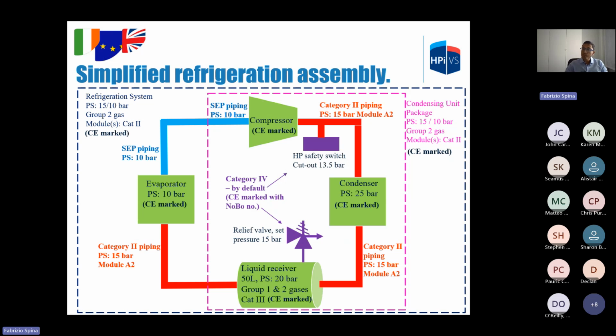This is a simplified refrigeration assembly. We can start with the compressor, already CE marked, so it is a bought item. We have the condenser, already CE marked, so it is another bought item. The liquid receiver, CE marked, so bought item. Category 3, PS 20 bar, suitable for group 1 or group 2 gases. The evaporator is a bought item already CE marked, so these 4 pieces of equipment are already CE marked. The piping, which is made by the manufacturer within the assembly, is a manufactured item. So the manufacturer needs to submit this piping to a conformity assessment.